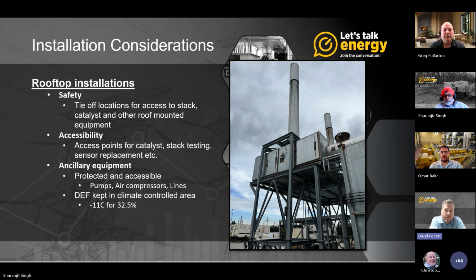As Greg mentioned with stack testing and compliance testing, you have to get up to the stack, get up to the controls on the side of the SCR, and inspect the catalyst. When you don't have a proper tie-off location or a proper way to access that port, you may end up renting man lifts and working with engineering firms to make access safe, which can cause delays in an emergency and added expense down the road.